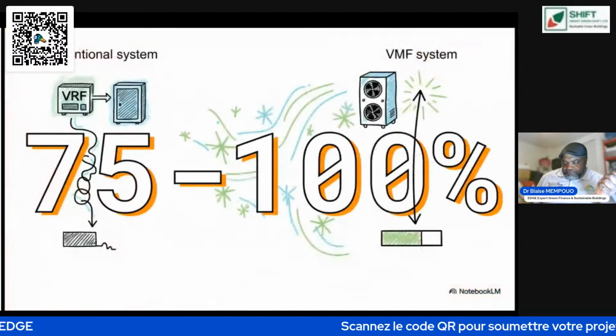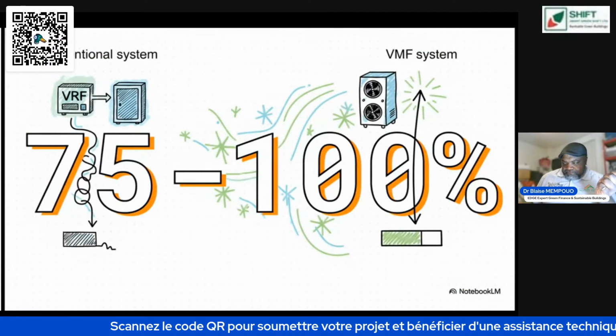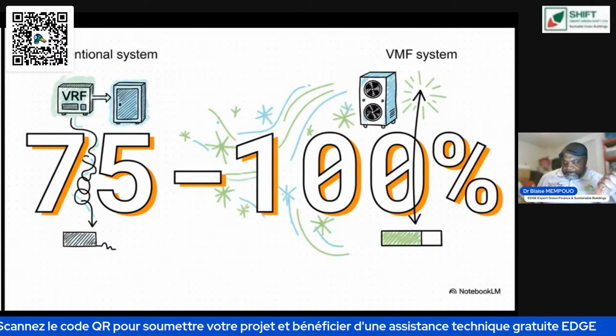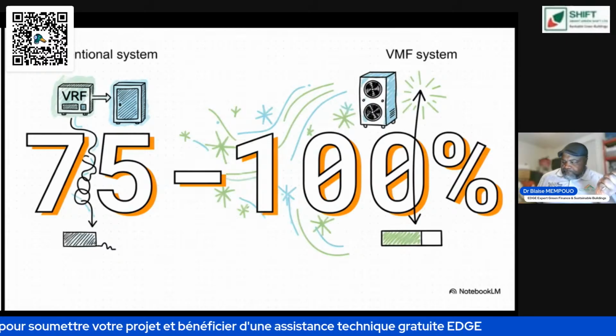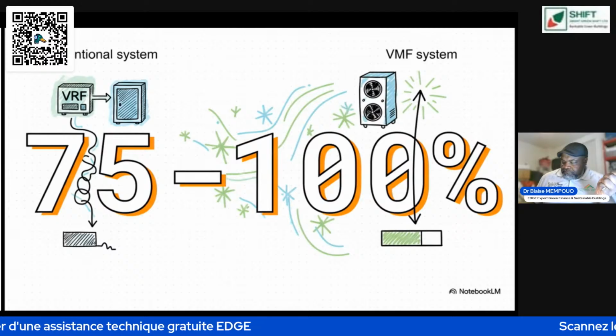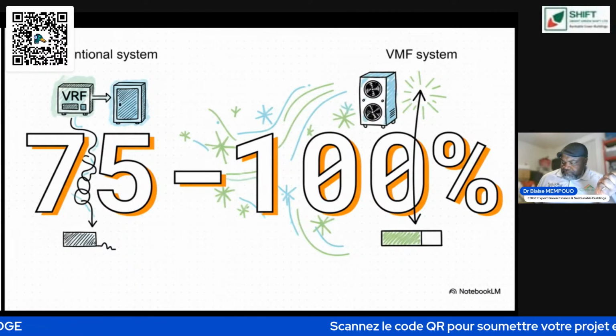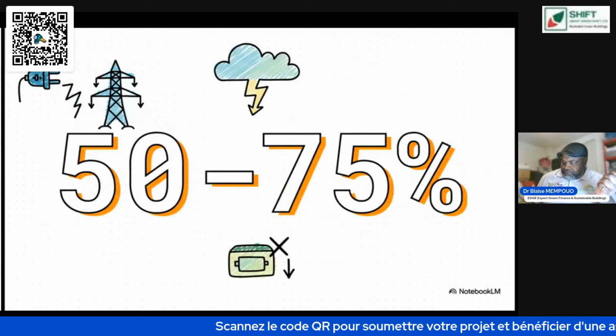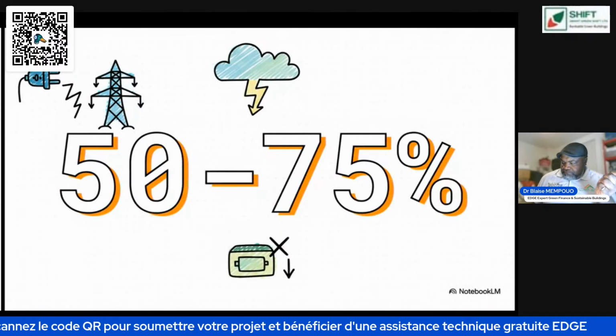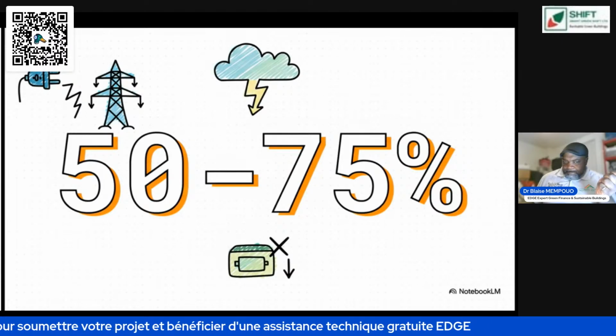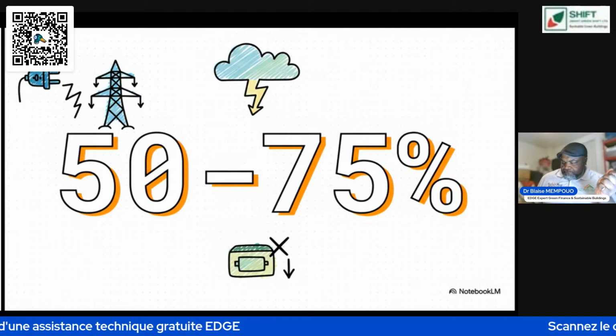Let's get into the numbers because they are pretty dramatic. Compared to a standard conventional system, the kind with separate refrigerant units and big air handlers, a VMF system can use 75 to 100% less energy. No, that is not a typo. We're talking about, in some cases, doubling the efficiency. It's wild. And because it's so much more efficient, it just needs way less power to run in the first place. The total power you need to install can be 50 to 75% lower, meaning less stress on the power grid and way smaller requirements for expensive backup power systems.